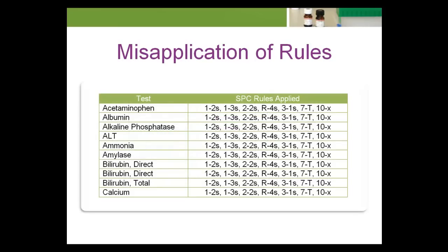Another practice is the application of the same single rule or multi-rule to all tests, regardless of instrument or method. This is done because it makes QC easier to manage. However, with the rules not reflecting test performance in relation to stability, sensitivity, and specificity along the method curve, unnecessary error flags, run rejections, recalibrations, and repeat testing is caused.